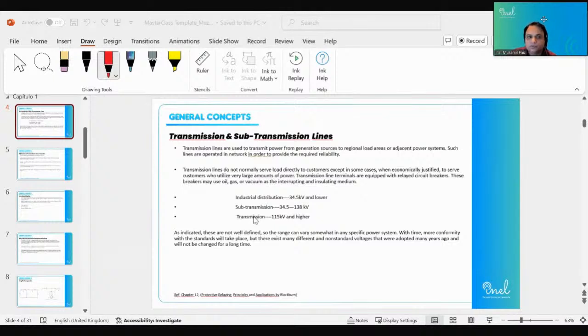There is another classification which we usually have in books. If the transmission line is less than 80 kilometers, it is considered a short transmission line. If it is between 80 and 250 kilometers, we say it is a medium transmission line. And if it is greater than 250, we usually consider it a long transmission line. So there are two types of classification of transmission lines: one is on the basis of their length, and the other is on the basis of the voltage level at which they are operating.